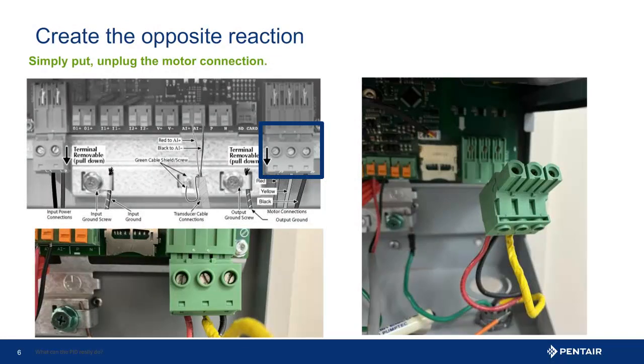Now we proofed the program. The next step with a high amp fault is to turn the drive off and carefully unplug the motor connection shown here. Have the motor plug in a position that it will not contact any part of the drive and restart the drive. Clear the fault and press auto start. Wait. Do you get another high amp fault? Well, if no motor connected and you still see a high amp fault, it is most likely the drive. If you get a low amp fault, well, it is time to test the motor.